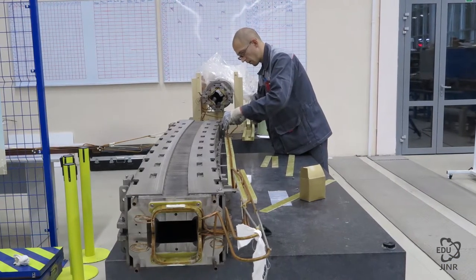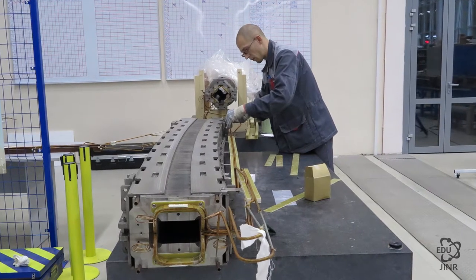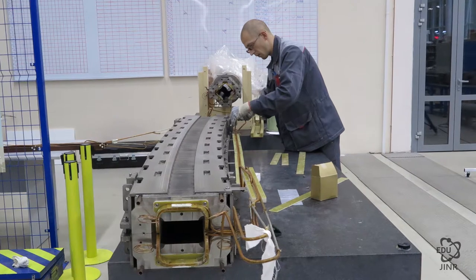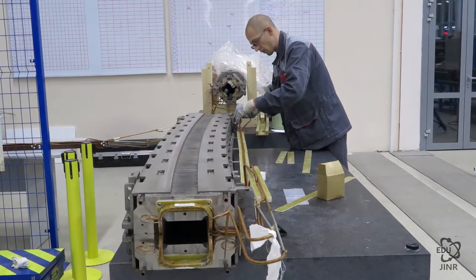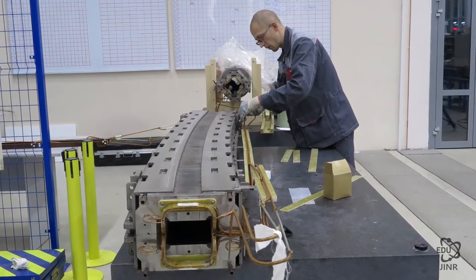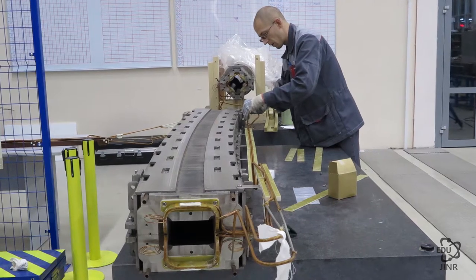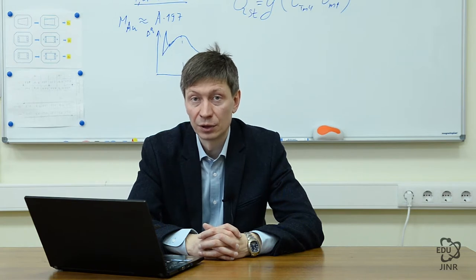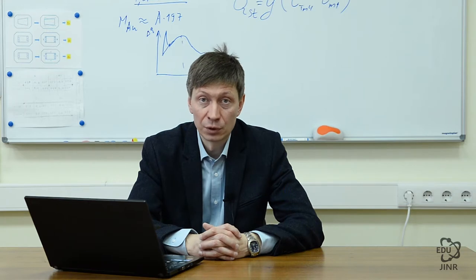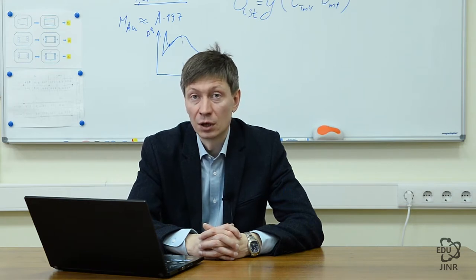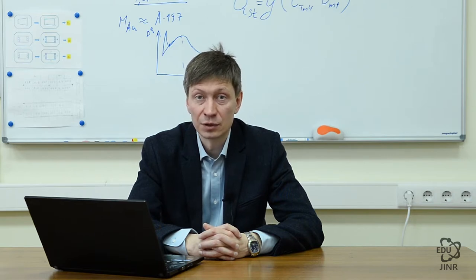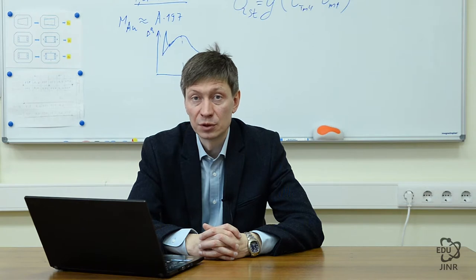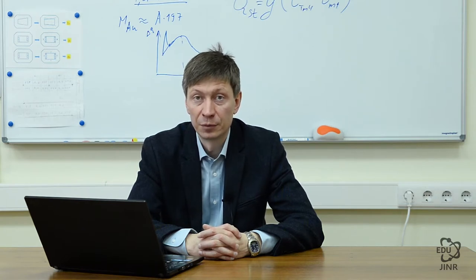After the level of perfection of the superconducting winding and iron yoke has been confirmed by the results of the warm measurements, the magnet returns to the mechanical area for final assembly. All helium tubes are combined into a whole system, insulators are soldered in, potential end pins are soldered on, and helium collectors are installed. After all helium tubes have been soldered into a single system, an air tightness check of the tubes with circulating refrigerant coolant takes place. Following the re-inspection of the electric characteristics of the winding, the magnet is balanced on a special suspension inside the cryostat, and after the installation of thermometers, it is ready for primary testing — cooling and measuring parameters under liquid helium temperature.